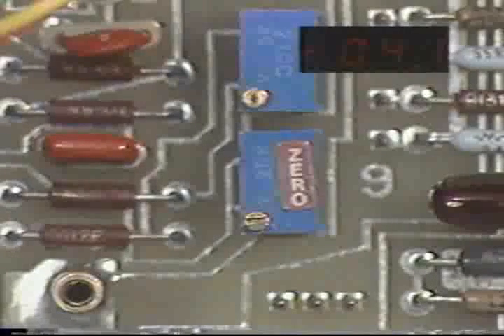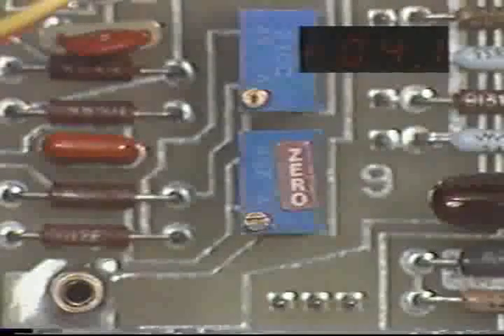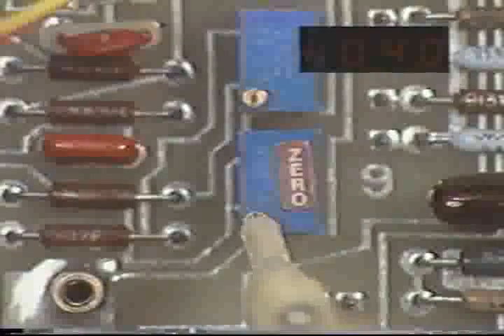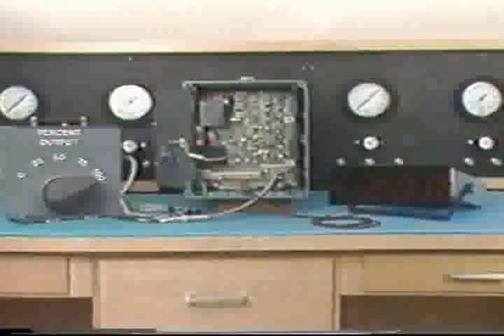The zero is adjusted at the lowest point in the instrument's range by turning the zero adjust screw until the output reading here is correct. Since zero and span often affect one another, we should verify the span. These readings indicate that the transmitter's span does not need adjustment. Now, to conclude the calibration, recheck the upscale and downscale readings to ensure that the instrument is properly calibrated.